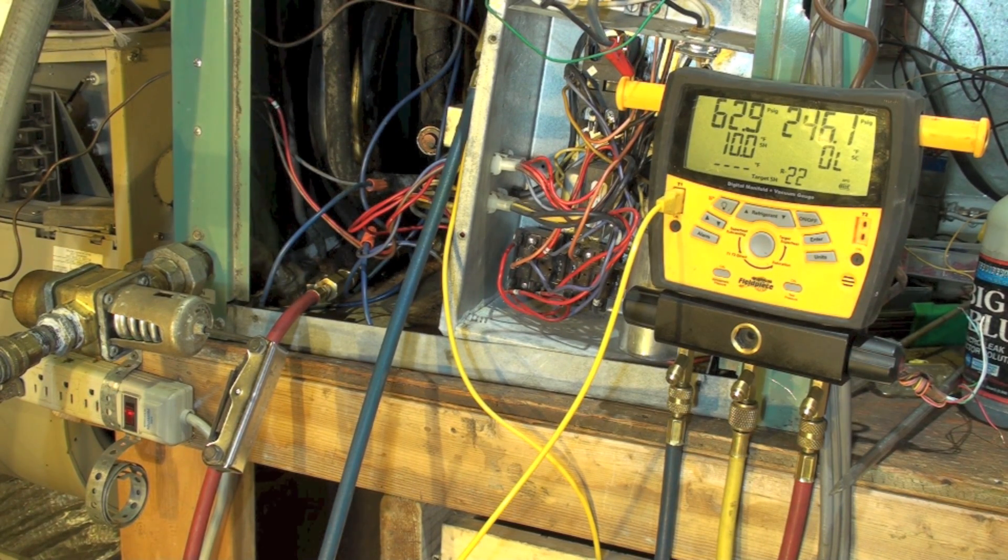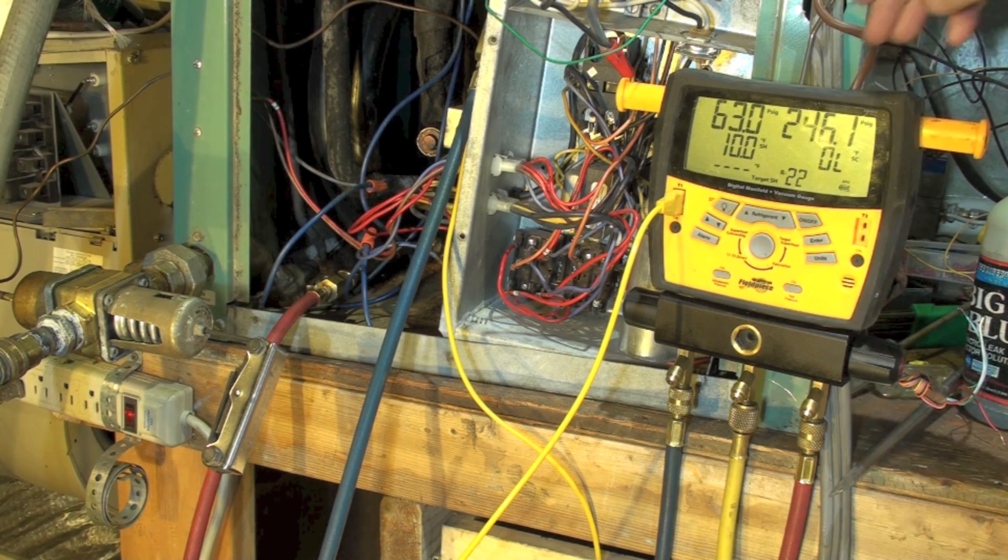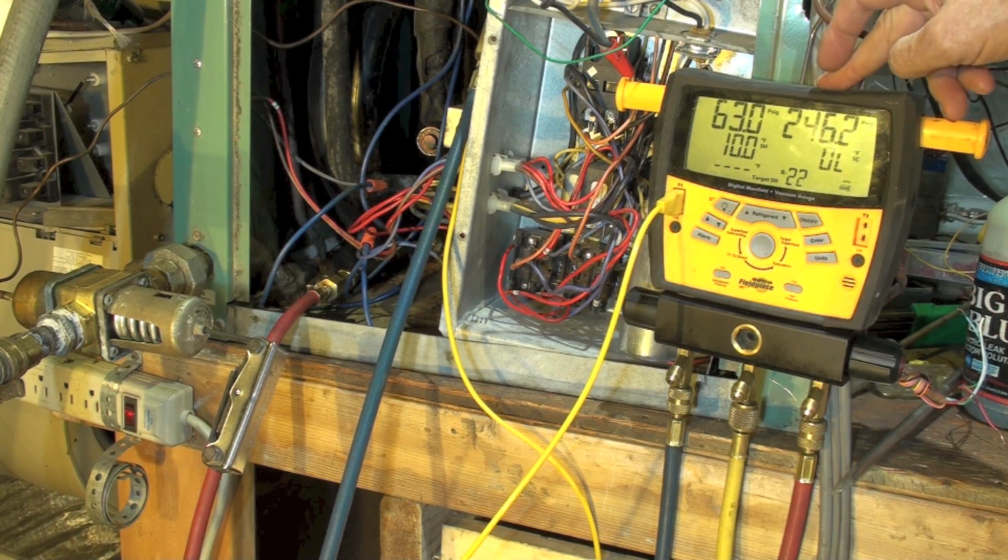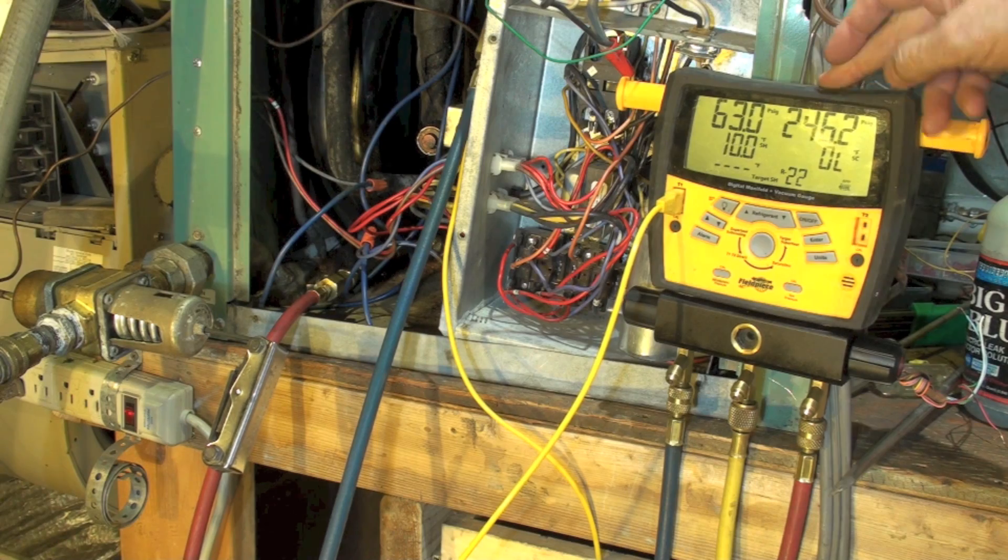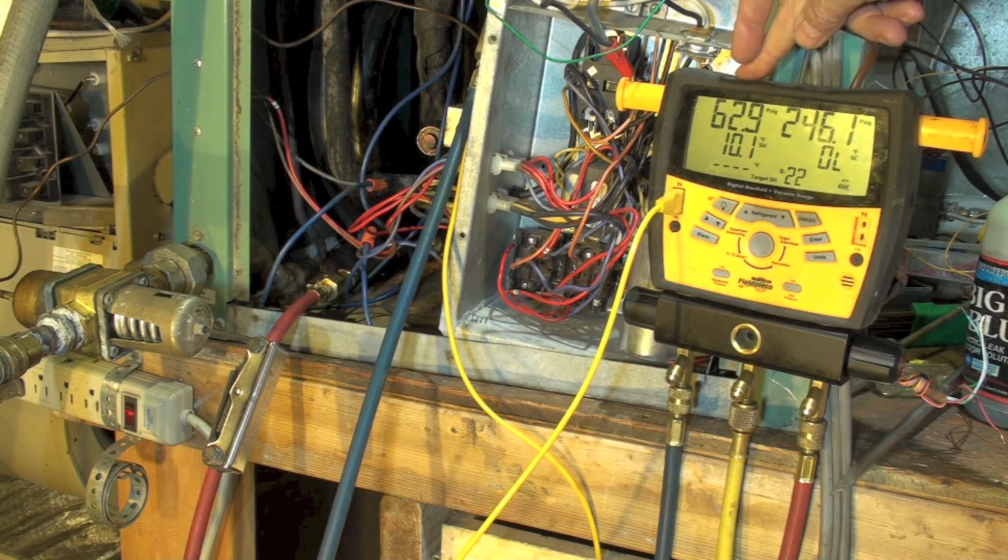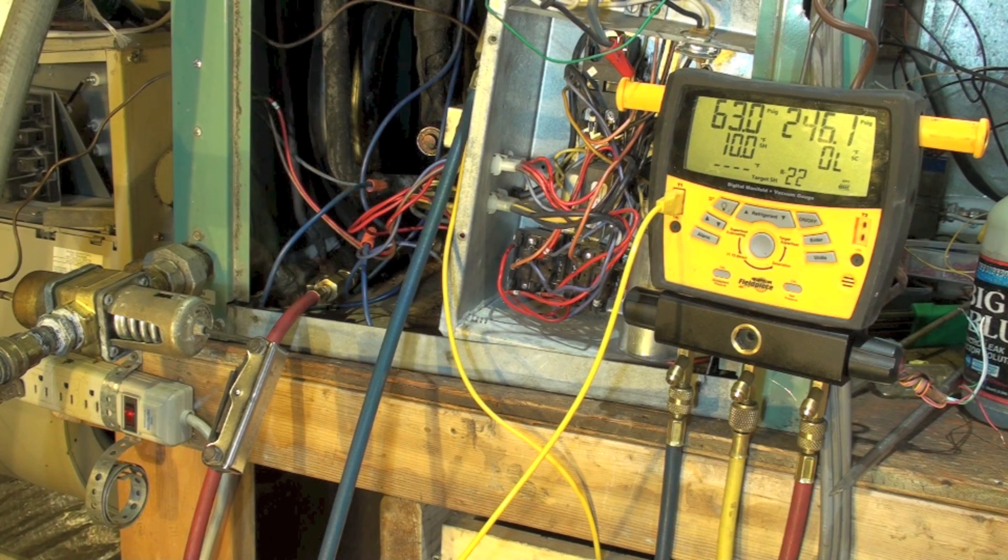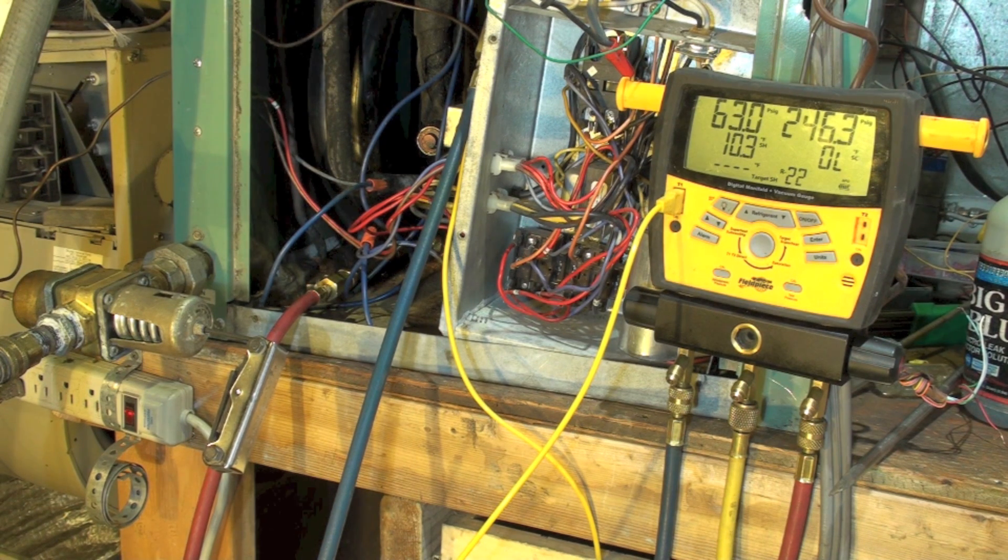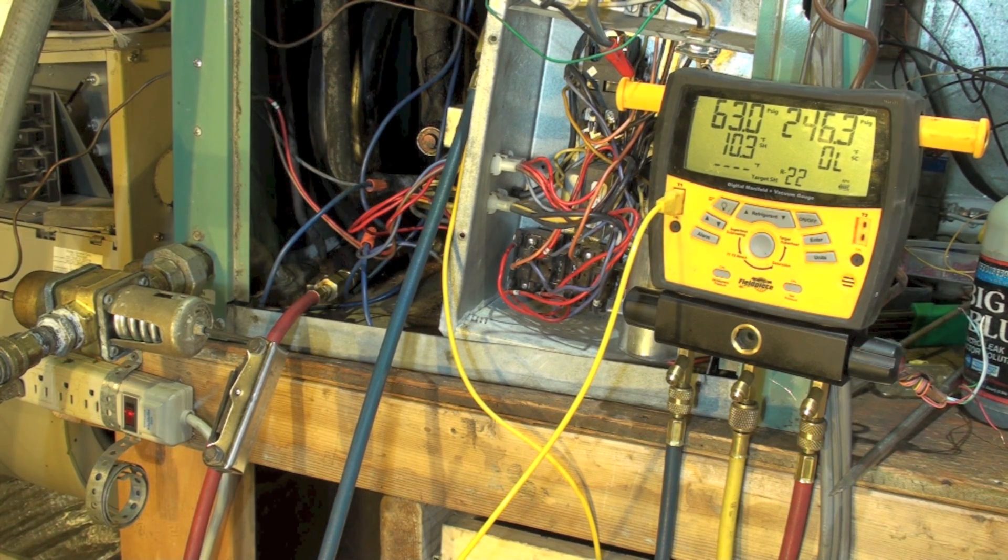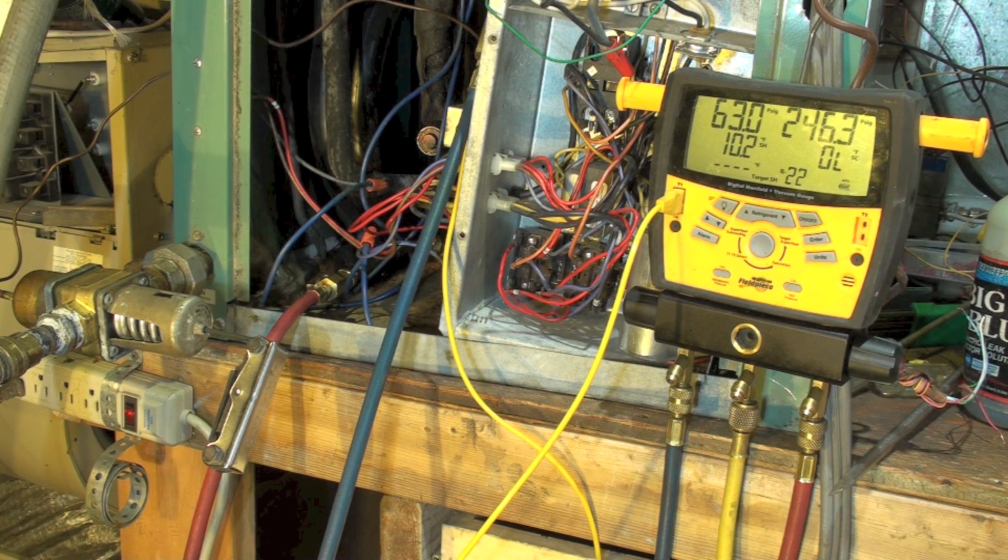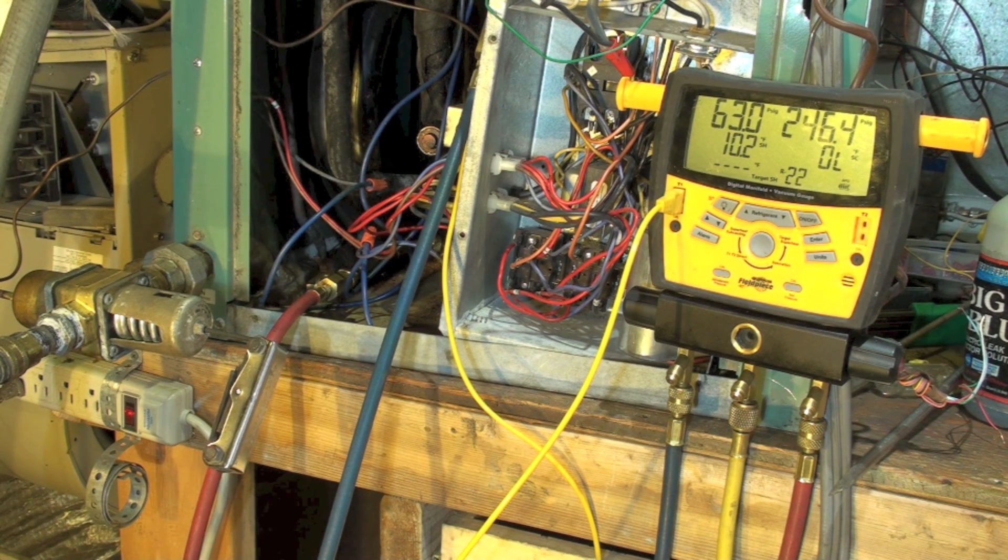Okay, let's jack the pressure up a little more. With all my whittling and piddling with this thing, my final numbers on this are 246 on the head - seems kind of high - 63 on the suction. We've got about 10 degrees of superheat, and our discharge water temperature is 102. Now if I was setting this up, this is how I would set it.